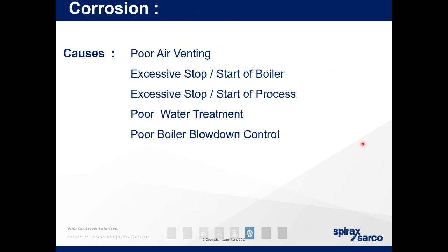Poor water treatment, as we covered before, so the particulates that you find in that water, and poor boiler blowdown control. Again, we can never eliminate all particulates in water unless you have a pure steam demineralized water system. You will get particulates, which means you will need to blow down. So you remove that sludge at the bottom of the boiler, which normally accumulates around the fire tube, and would prevent heat transfer to water from the fire tube. So boiler blowdown is removing that sludge, removing those excess particulates in your boiler, so that it doesn't carry over, but also so you get more efficiency in the production of steam in your steam system.